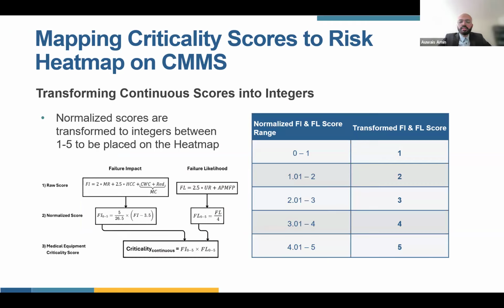What I tried to do in this case was to not compromise on the risk that a device might have. If a risk to a device from the scoring goes even a decimal above, say, for example, this lower limit of a 1, which was here, the transformation just takes it up to a higher risk score of 2. And so when these risks do get displayed, you're not under-reporting on the risk that we calculate.